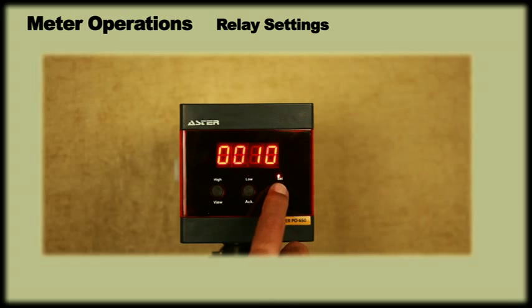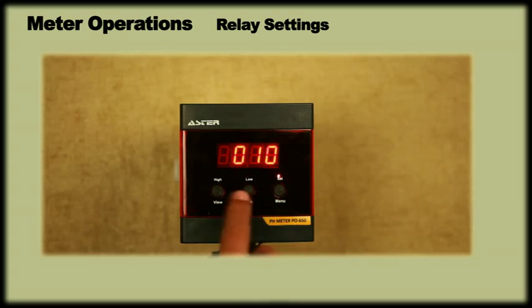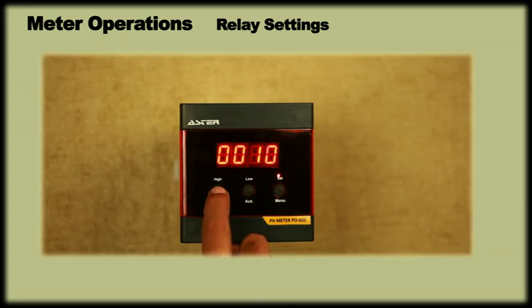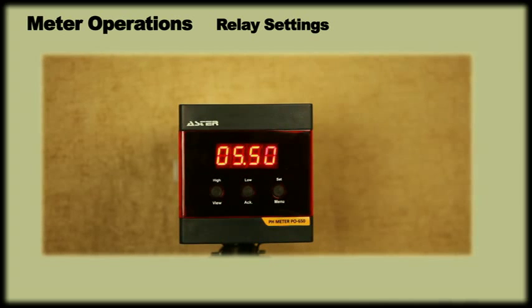On pressing menu, it will show a previously set hysteresis value. Using ACK key and view key, we can set the required hysteresis value. Let us set hysteresis value at 10% and press menu to enter. In this case, low set point is 5 with 10% hysteresis, hence the relay will get reset only when the pH goes over 5.5. Normally, hysteresis values are kept at 10%.